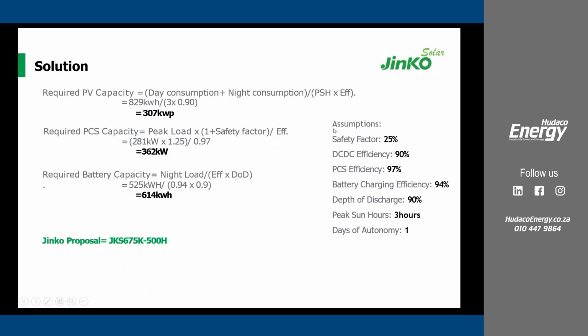Of course, we need to determine our assumptions in this case, including the safety factor of 25%. We also need to define the DC-DC efficiency. In AC coupled scenarios, we're looking at the PV inverter efficiency, so we also need to define that. We also need to know the PCS efficiency and the battery charging efficiency. We also need to know the depth of discharge: we are working with 90%, or even when working with the SunTerra or the SunGiga Air Cool, we've determined the depth of discharge at 94.5%. Then we also need to know the peak sun hours and the days of autonomy. So you can see all those factors that we need to factor in. We need to determine our assumptions for the purpose of the calculations.